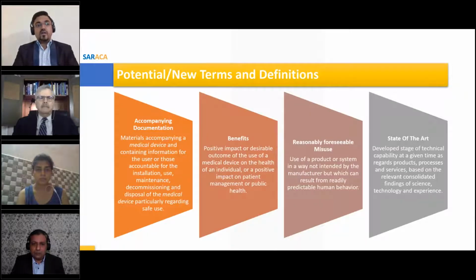Then I have listed a few new terms and definitions. These were introduced in the 2019 version, the third edition. The new terms are benefit, reasonably foreseeable misuse, and state of the art. I kept one potential definition as well, accompanying documentation. Let me explain what accompanying documentation is. It means all the labeling-related documents that go to the user with the medical device and are used from the installation phase to the decommissioning or disposal phase, meaning from installation to use, how you use your device, how you decommission it, or how you dispose of it. All these instructions written in a document are called accompanying documentation.